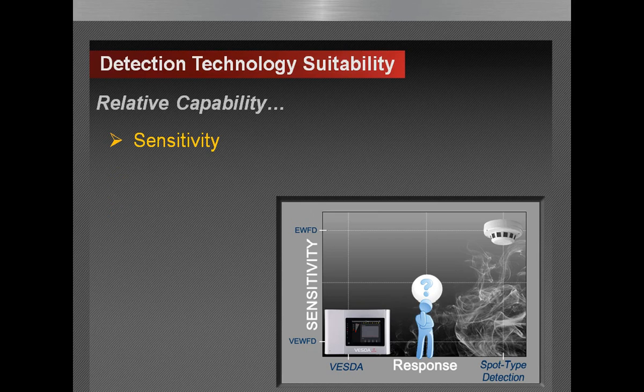The unique environments within IT communication infrastructure present a challenge to both early and reliable fire detection. Conventional and prescriptive methods, technologies, placement, and spacing can be challenging, if not impossible. Selection of a particular technology is based on the technology's suitability to effectively perform its intended function within the sensitivity objectives. So sensitivity is a key factor in detecting fires at their incipient stage, allowing early intervention for investigation and action, potentially before smoke and corrosive gases affect equipment and personnel. And sensitivity is also key in overcoming the effects of dilution.